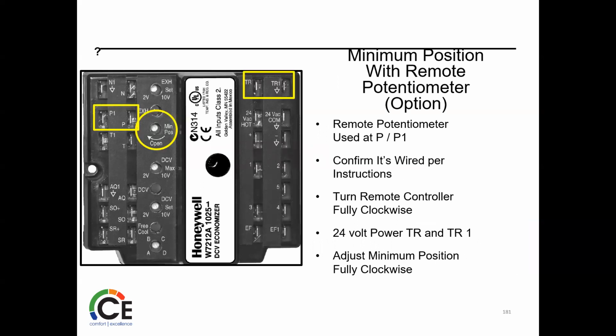So again, if we're testing this, power is the biggest thing. TR stands for transformer. 24 volts, right? Because we're powering 24 volts with everything at this point. So if you don't have 24 volts at TR and TR1, you've got to go back and figure out what's going on, because your economizer control is not powered. And depending on which economizer you have, some of them may be fully open, some may be closed. It doesn't matter. Now, of course, if you do have power, then as you turn this potentiometer, you should eventually see activation.